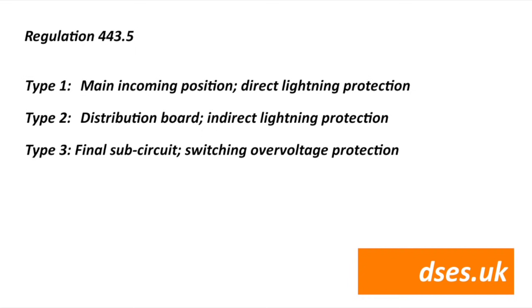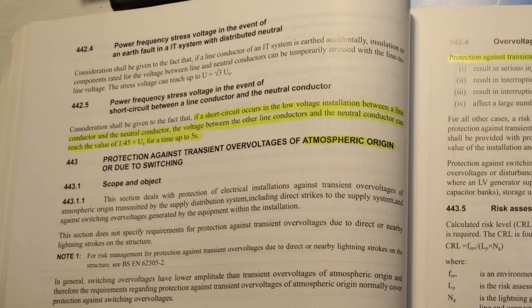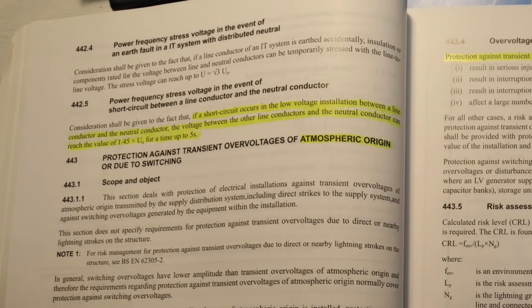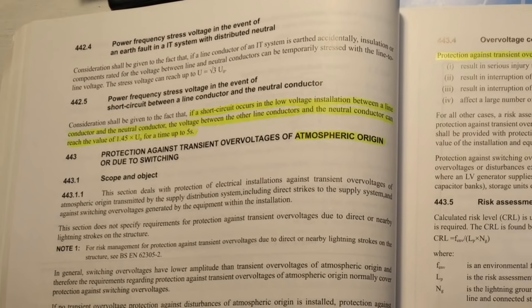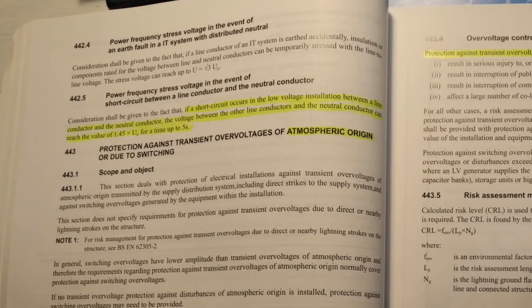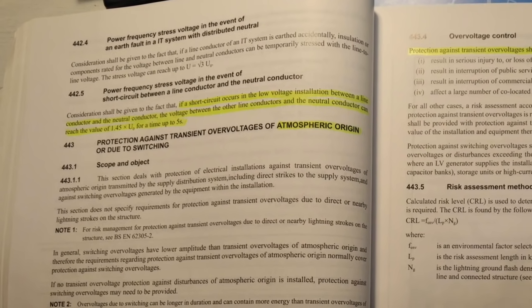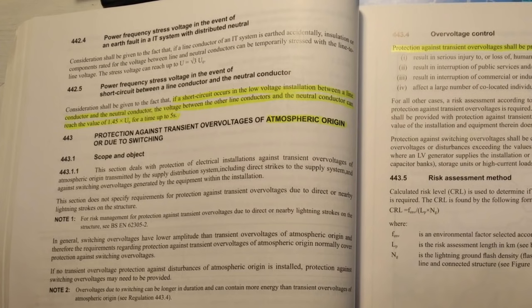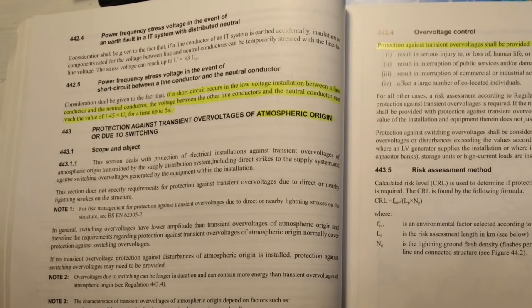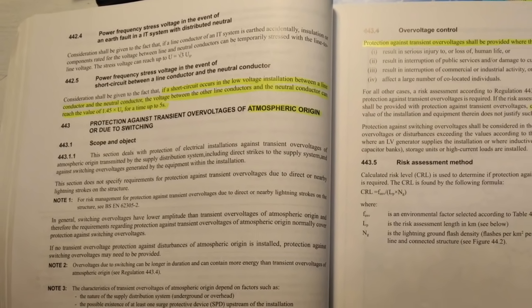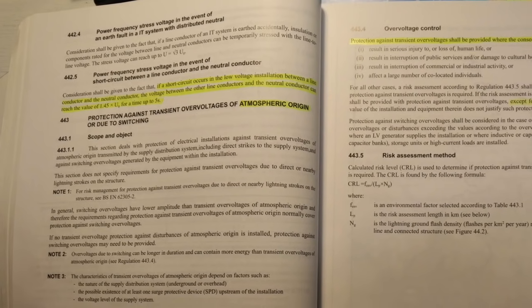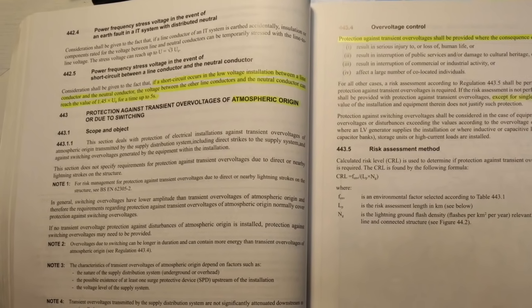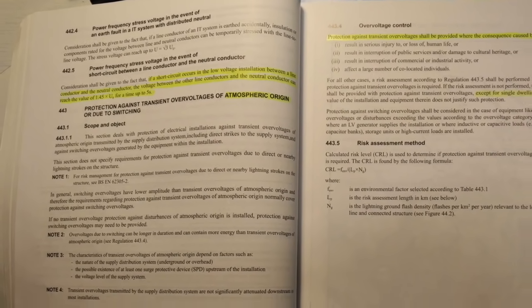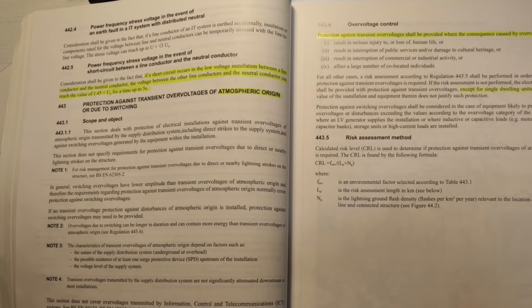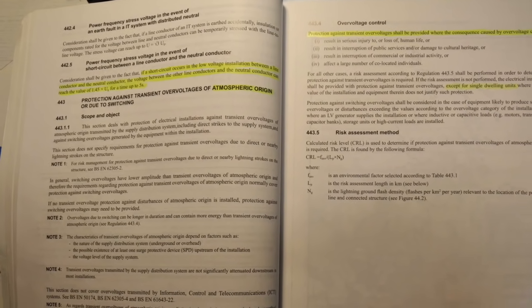Incidentally, this device is suitable for both TN and TT installations. 18th edition Regulation 443 is what we're interested in, and in its own roundabout way it says that if you're covering an installation from surges caused by atmospheric conditions, then you'll likely also be covering it against switching overvoltages, which are normally lower in amplitude. This means that by installing this device into my consumer unit I should be protecting my own installation adequately enough for whatever me, the bloody wife or Mother Nature can throw at it.